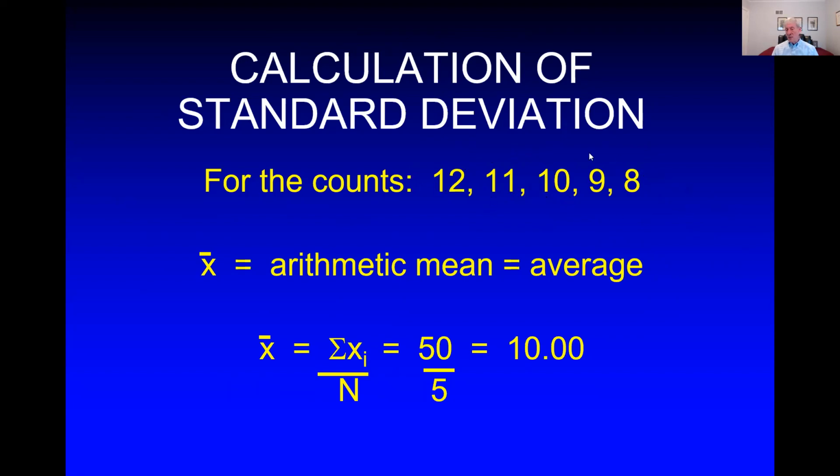If I add all these up and divide by 5, I get exactly 10.00. It's accurate. But what can you say about precision? Terrible, right? You don't have good precision here. You have 0% error, 10% error, and on these two, 20% error. That's terrible. So we have an accurate by accident dose calibrator that is totally imprecise.